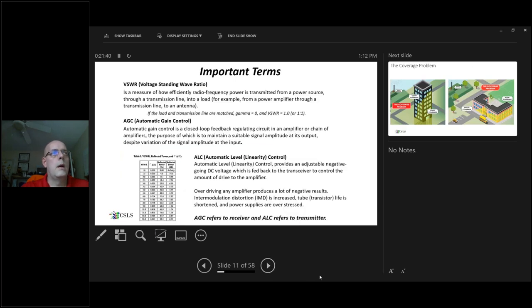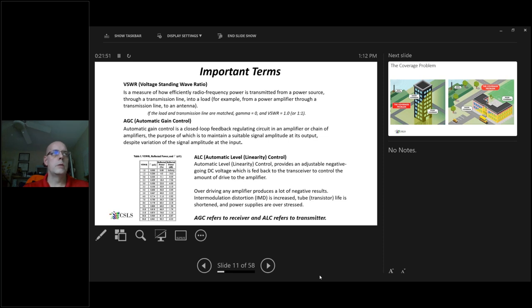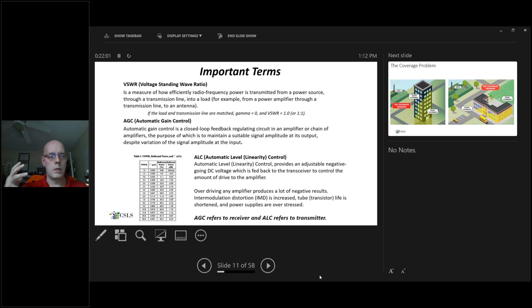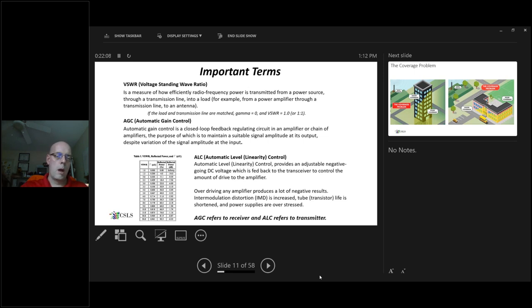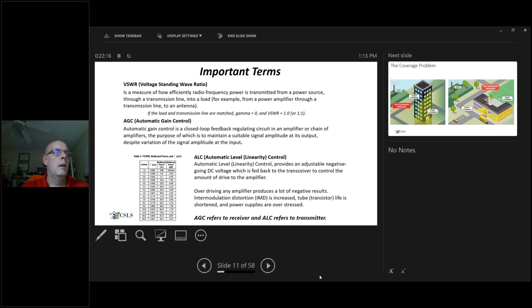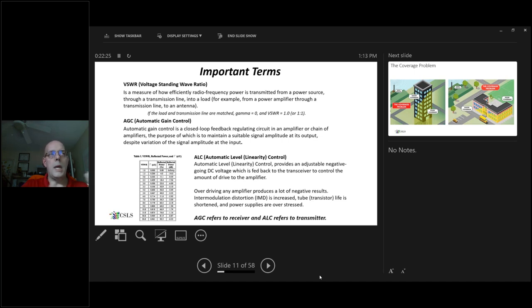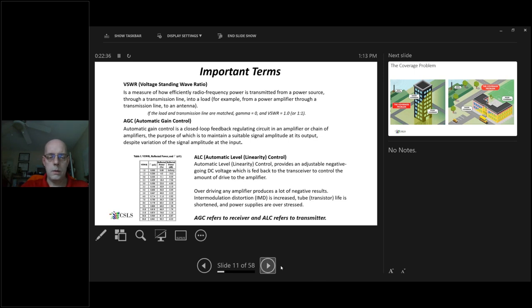Important terms applicable for installations and fire marshals doing inspections. VSWR is voltage standing wave ratio. That's a measurement of the efficiency of radio frequency power being transmitted from a power source. At the macro level, it's the towers we see along the road. At the micro level, it's where we're installing a bidirectional amplifier system receiving signal and transmitting back to the tower. AGC is automatic gain control, a closed-loop feedback regulating circuit in an amplifier or chain of amplifiers. We look at AGC on the receiving side, and ALC, automatic level control, on the transmit side. Key terms get really heavy into the science. I don't want to get too far down the road, but if you have questions, please reach out to me.